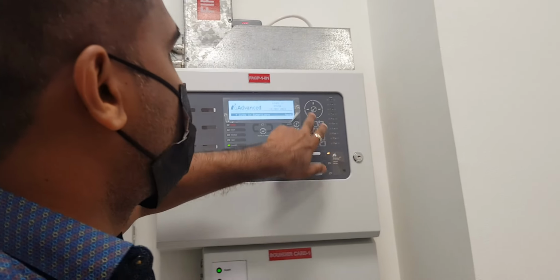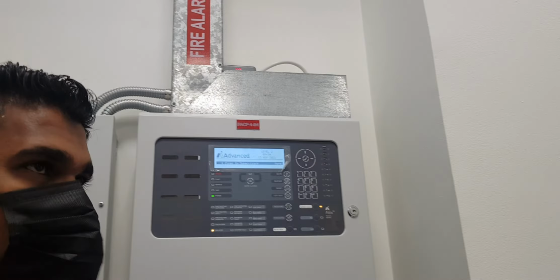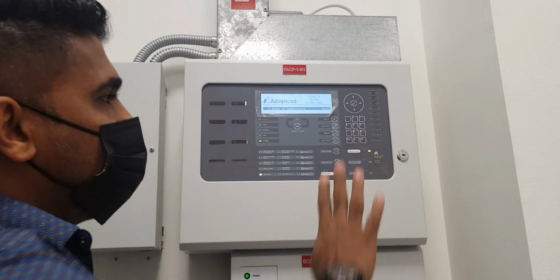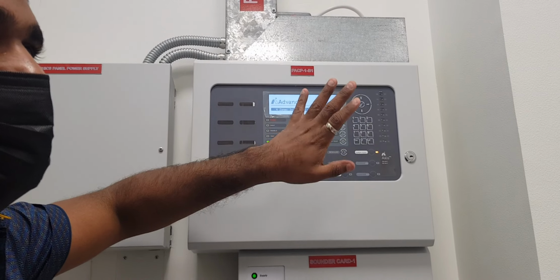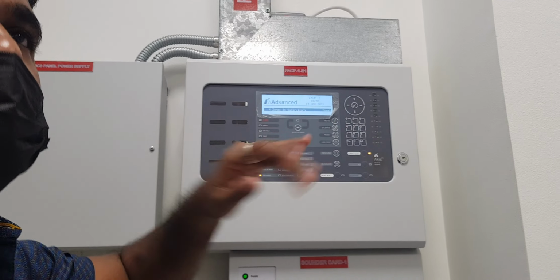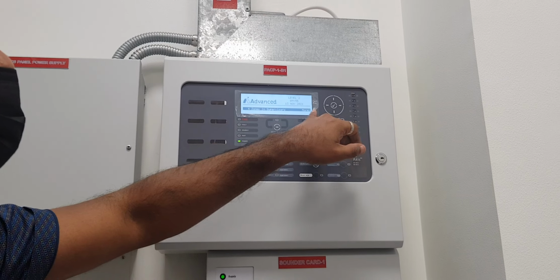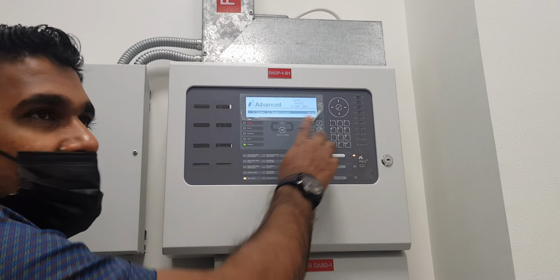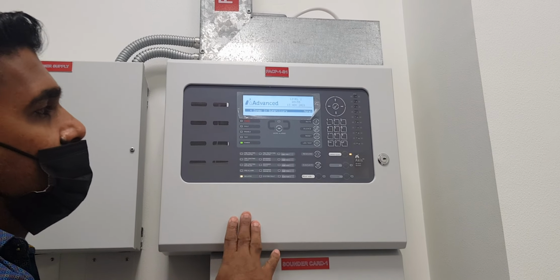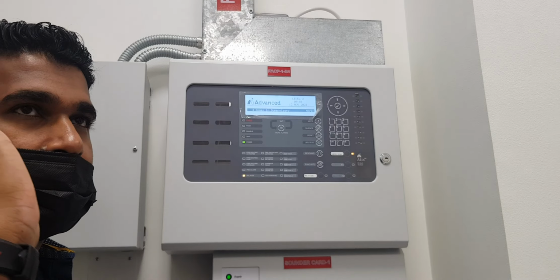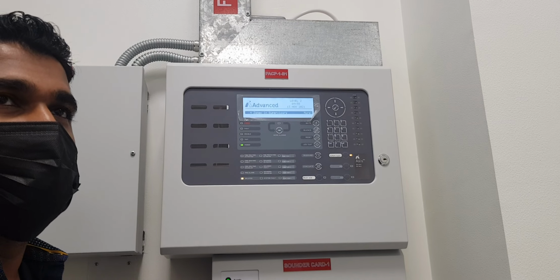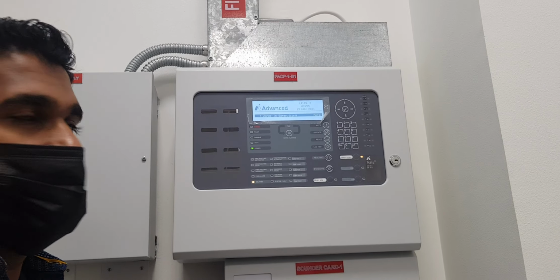So basically, as a user, you have these buttons. I've given a sheet also for that. These are the main buttons which we will be using, apart from us, because we have internal ones there. For you guys, it will be these buttons. When any alarm comes, the buzzer will come on in all the panels. To stop the buzzer inside the panel, you have to press mute, just for the internal buzzer. Silence is for the alarm system. Reset, do it only if the alarm is clear, otherwise it will keep coming back.